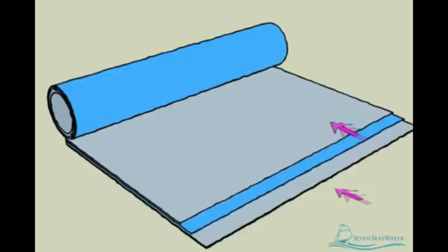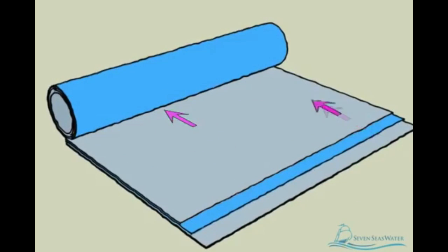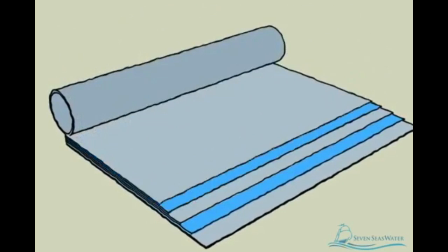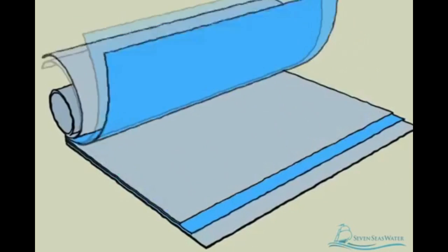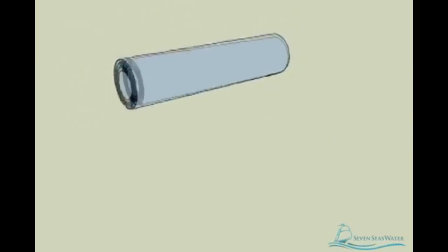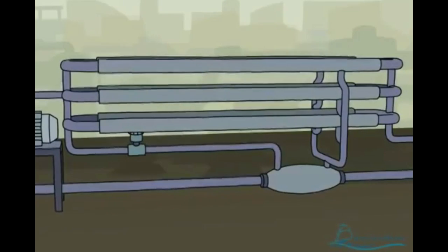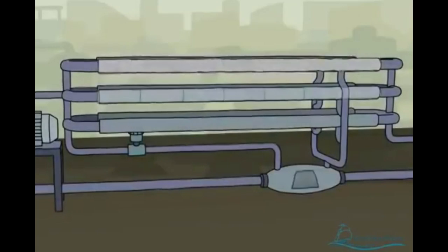The reverse osmosis membrane can be thought of as a number of sealed envelopes connected at their open ends to a tube. There are spacers between each envelope which allow water to flow across the membranes. The membrane envelopes and spacers are then wound around the tube like a roll of paper towels. The reverse osmosis membranes are then enclosed in a fiberglass shell, connected end to end — usually six to seven membranes together — and housed in vessels that are built to withstand pressures up to 1,200 psi.